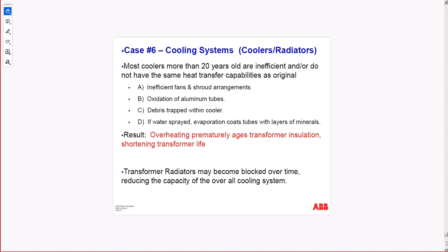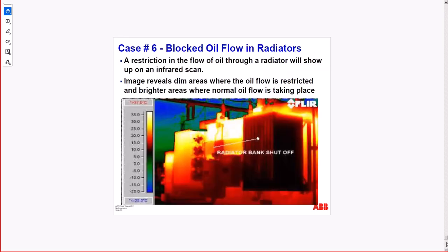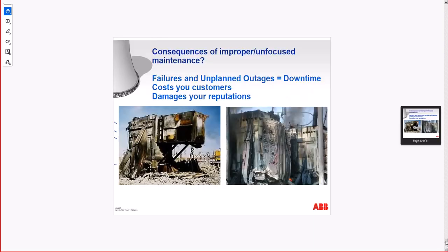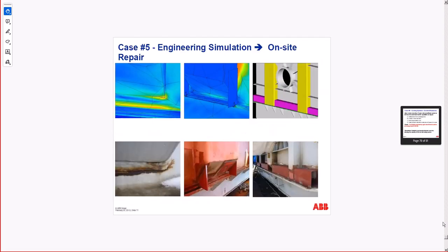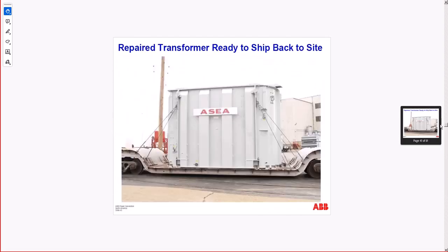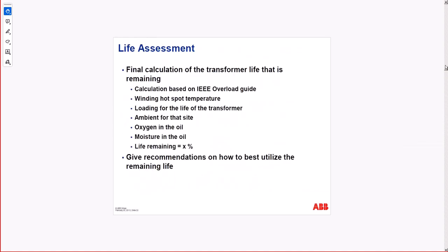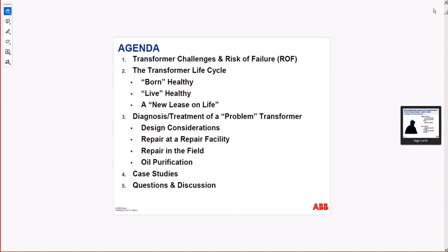Coolers, 20 years, need to be replaced, typically because of the debris and trapped sludge, blocked oil flow. You can see the over temperature in a certain place and so on. And this is a failure for a transformer, complete failure, and so on. So this was the ABB presentation.